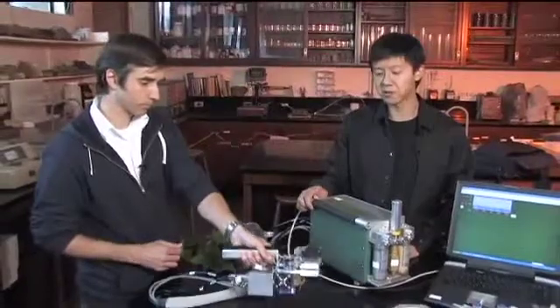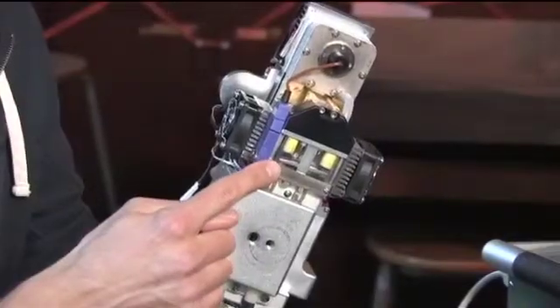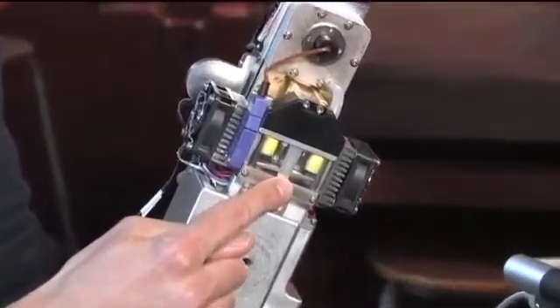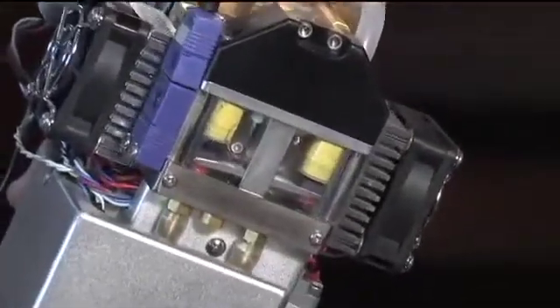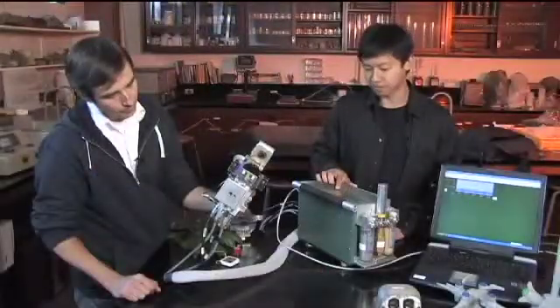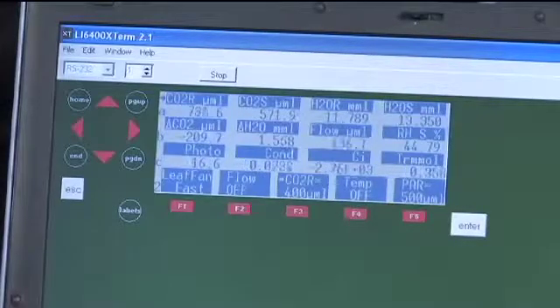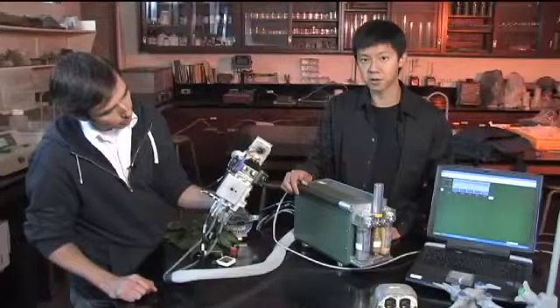The first step for measuring a leaf is to match the two sensors, the sample and reference. Because we're interested in the difference between the reference and sample measurements of CO2, it's important that the two sensors can measure the same value for the same air that's flowing. So we will match right now. It takes about one or two minutes for the system to match itself to wait for the CO2 levels to equilibrate.